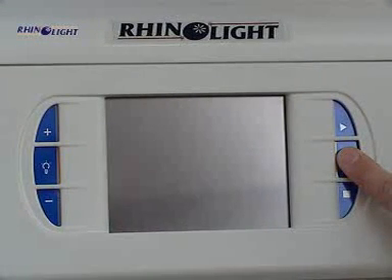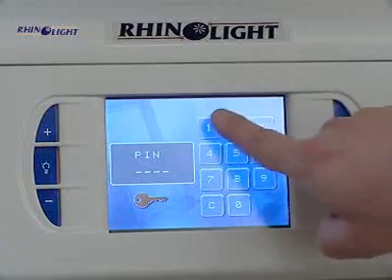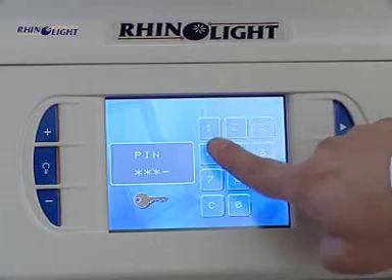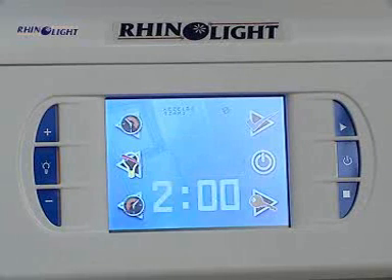Following this, pushing the button on the LCD touchscreen display shows that the equipment is ready to receive the PIN. This four-digit code allows only authorized medical personnel to start the device. After receiving the PIN, the equipment provides the person switching on the device a welcome note by name, and the menu is shown on the display.